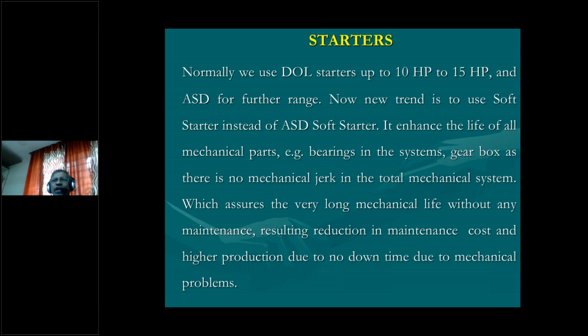And what are the opportunities? The saving. Now, if you take one water pump, say a water pump of 40 HP, many times water pumps are the most vulnerable, which can be used for an application of VFD. See what happens. The selection of a water pump depends upon your flow and your head. Suppose you require say 500 liters per minute, and your head is say 20 meters. You cannot get a pump which can match your exact requirement, which will give the output of 500 liters per minute with the head of 20 meters.